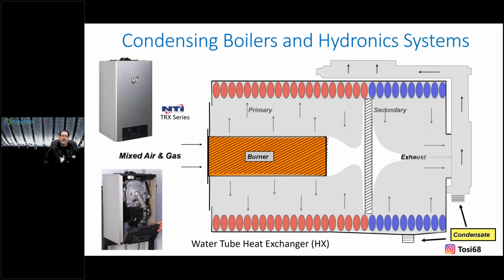If you're triggering a high limit, or you're getting constant faults or even a lockout, that's because of maintenance. You need to understand that heat exchanger is now maybe sooted up, or just needs to be cleaned, right? Because I'm not getting that heat energy into the water. It's being restricted. There's somewhat of an insulation, and now that burner is saying, hey, I'm not able to take the heat into the water, and therefore we have safety. So they pop, and maybe we just reset, and 2 weeks later, a week later, 3 days later, in a short period of time, it just reoccurs over and over again. So the lack of maintenance, or the need for more maintenance, is there.